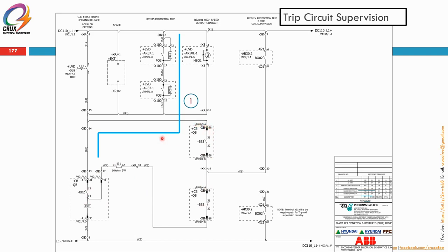So when the breaker is in the closed condition, BB2 normally open and BB3 normally open become closed, and BB2 normally closed becomes open. So after the breaker is closed, the monitoring is being done through this relay. It is monitoring the RET615, which is a protection relay for transformer. There is an internal resistor, and also another internal resistor at this relay, AR87, which is a differential relay. So the monitoring is through this contact coming here, going directly through the coil. So this circuit is only monitoring the trip coil under breaker closed condition. When the breaker is in the open condition, it's not monitoring at all.